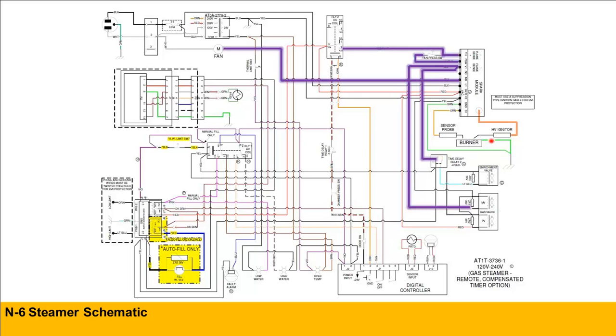We are not getting a spark at the igniter, or we're getting a weak flame sense. That could be due, once again, to no gas, low gas, or possibly a defective flame sensor. Or it might be going back to the module where the internal circuit that reads that flame sense is not picking up the DC microamps.